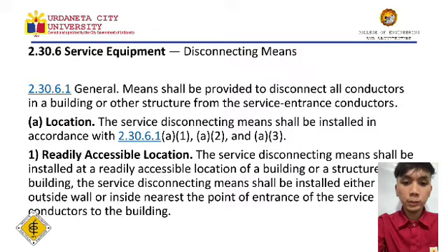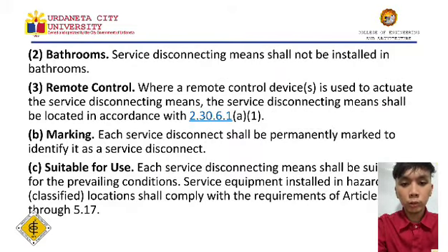For the location, the service disconnecting means shall be installed in accordance with the electrical code. First is the readily accessible location. The service disconnecting means shall be installed at a readily accessible location of a building or structure. For a building, the service disconnecting means shall be installed either at the outside wall or inside nearest the point of entrance of the service conductors to the building. Second, for bathrooms, service disconnecting means shall not be installed in bathrooms. Third, remote control. Where a remote control device is used to actuate the service disconnecting means, the service disconnecting means shall be located in accordance with the electrical code.